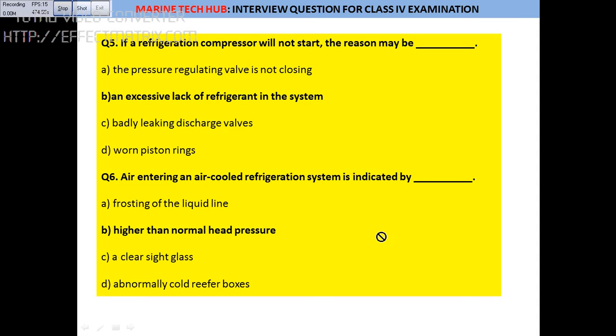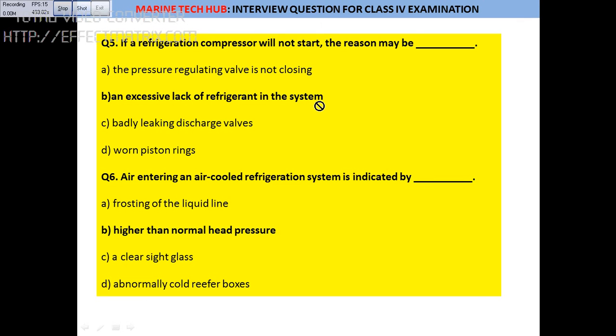Question 5: Why would a refrigeration compressor not start? There are many reasons, but one key reason is if there is a lack of refrigerant in the system. If there is very little gas, a low-pressure trip point will prevent the compressor from starting.